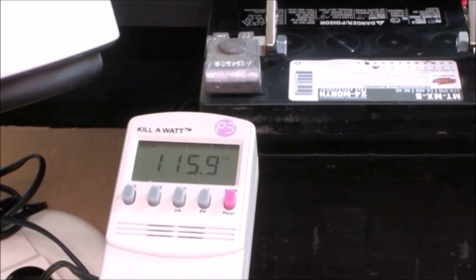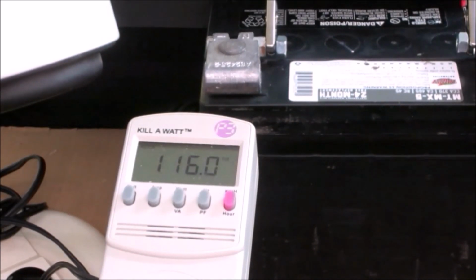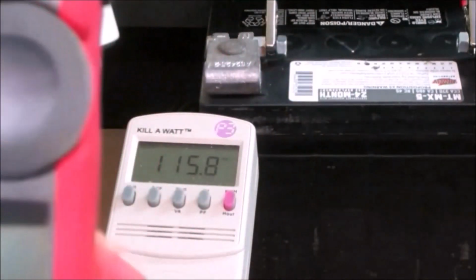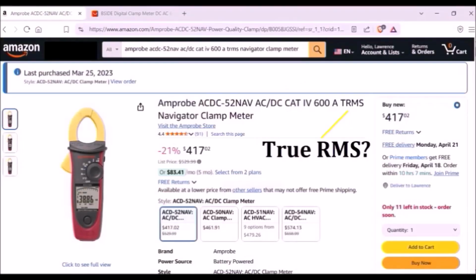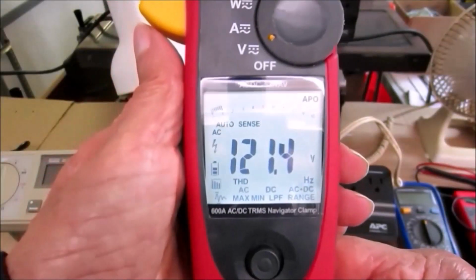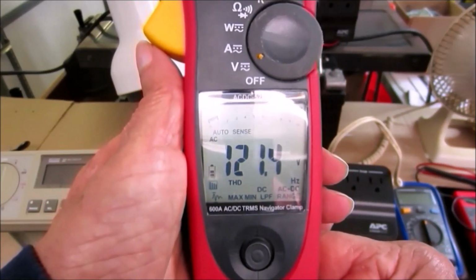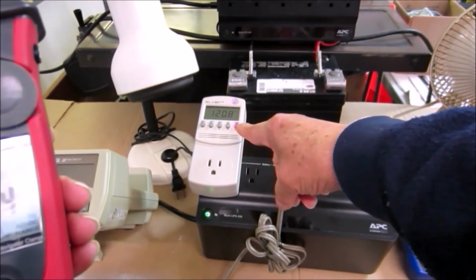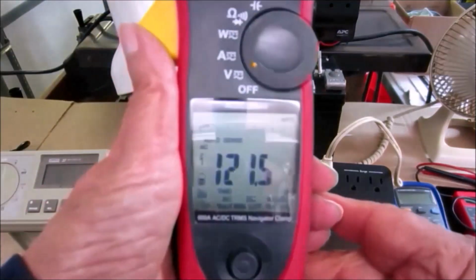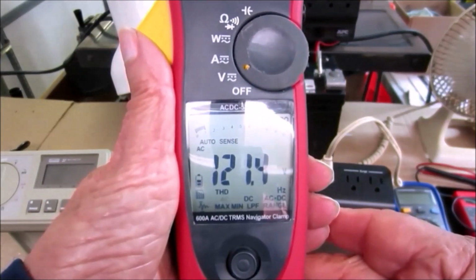Okay, that's only 20 bucks. Here's my amp probe. This amp probe is close to $500. I've turned the AC power back on, and this amp probe is showing 121.3 volts, and my kilowatt is showing 120.8. So we have a slight discrepancy between the two true RMS meters. And you can hear and see the fan blowing up a storm here.